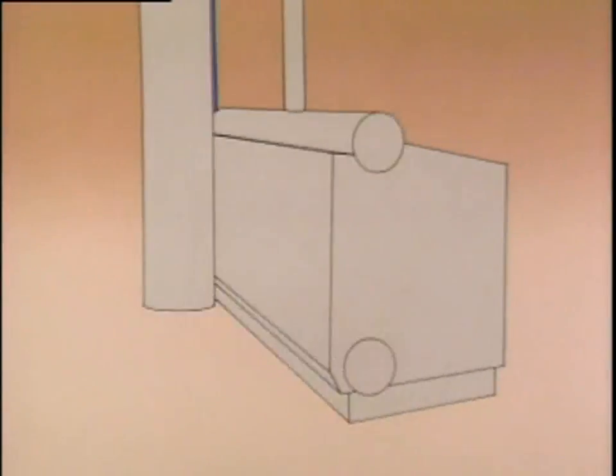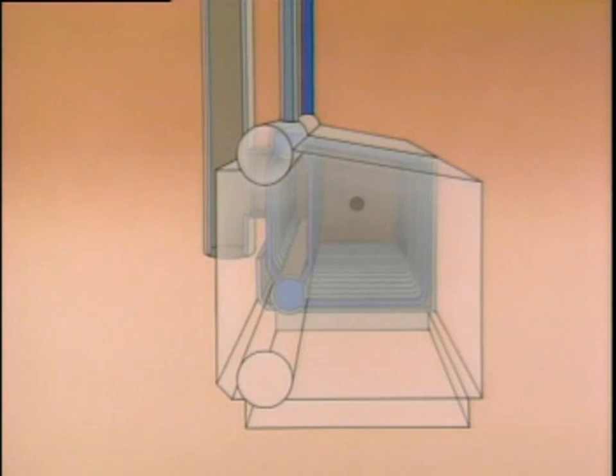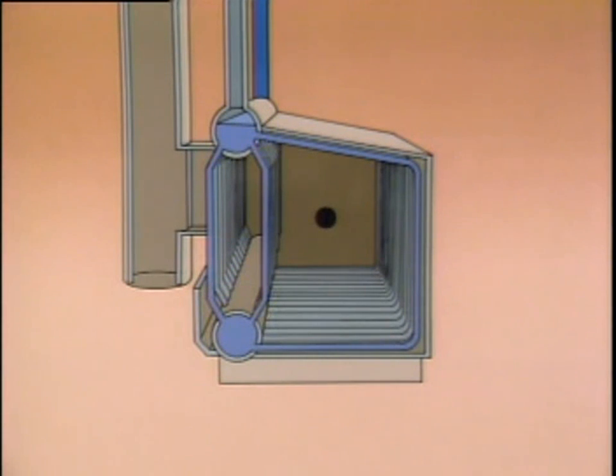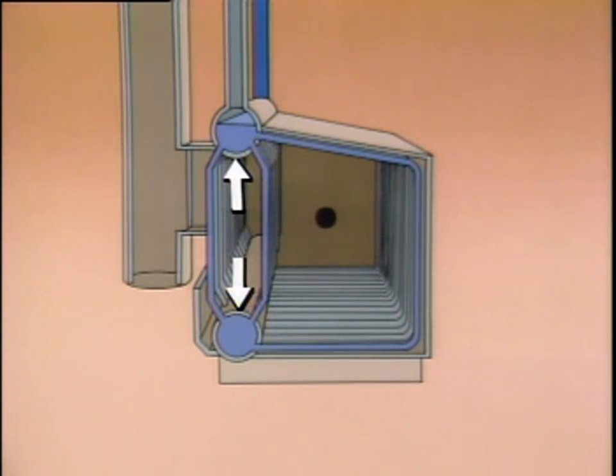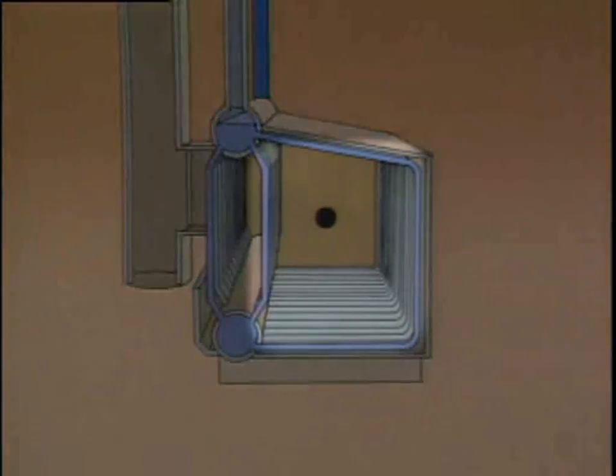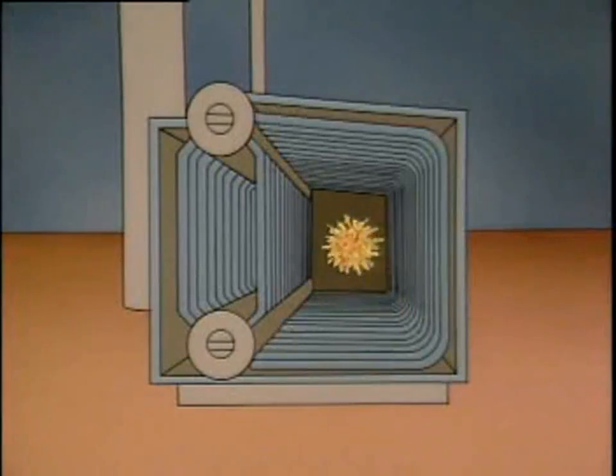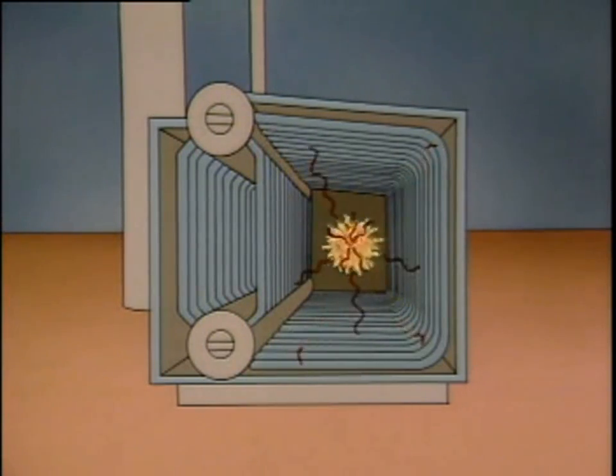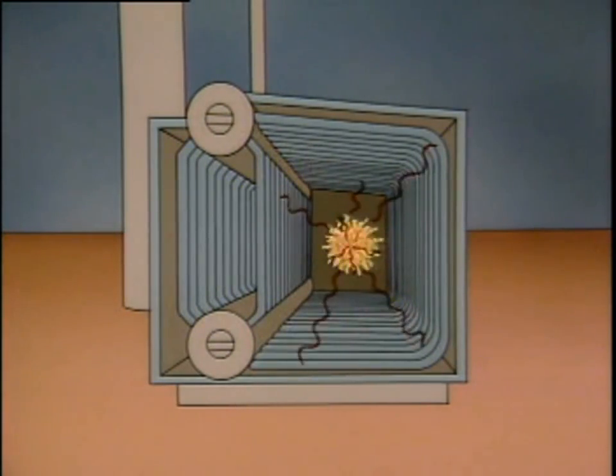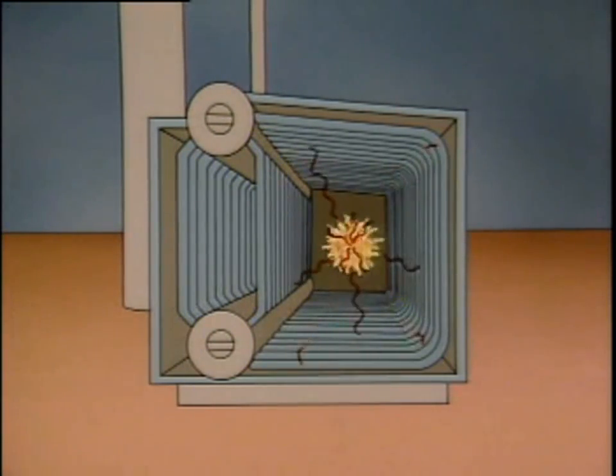This type of boiler is called a water tube boiler, but the heat transfer principles at work apply to just about all boilers. The boiler has a series of tubes and two drums which distribute water to the tubes. The tubes form a wall around the combustion area — the area where heat is generated. When fuel burns in a boiler, radiant energy in the form of electromagnetic waves is produced. These waves travel through the combustion area, and the waves in direct line of sight with the tubes make contact with the outer tube surfaces, and the tubes absorb heat. This is radiant heat transfer.